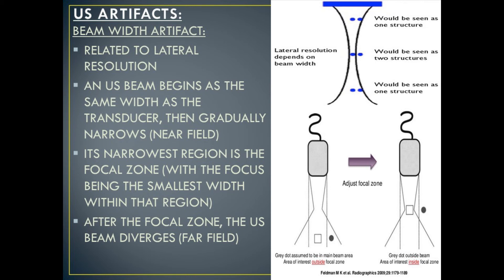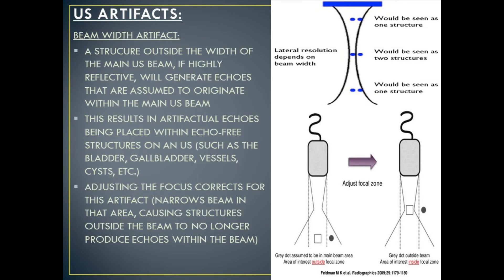Beam width artifact is related to lateral resolution. An ultrasound beam begins as the same width as the transducer and then gradually narrows in the near field. Its narrowest region is the focal zone, with the focus being the smallest width within that region. After the focal zone, the ultrasound beam diverges — this is known as the far field. A highly reflective structure outside the width of the main ultrasound beam will generate echoes assumed to originate within the main beam, resulting in artifactual echoes within echo-free structures such as the bladder, gallbladder, vessels, and cysts. Adjusting the focus corrects for this artifact by narrowing the beam in that area.